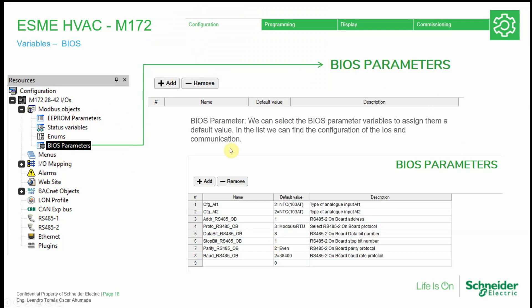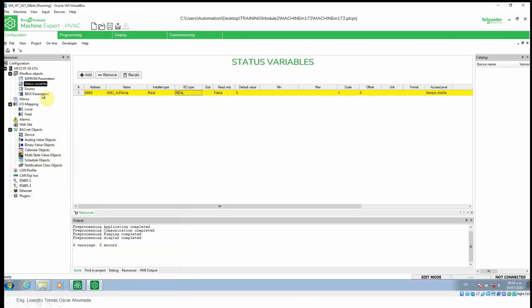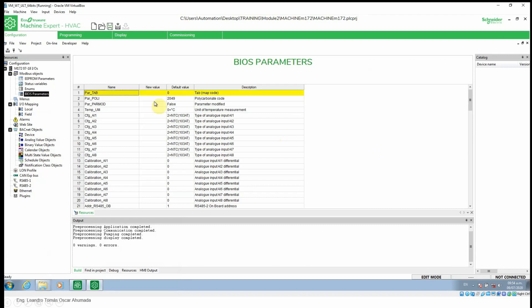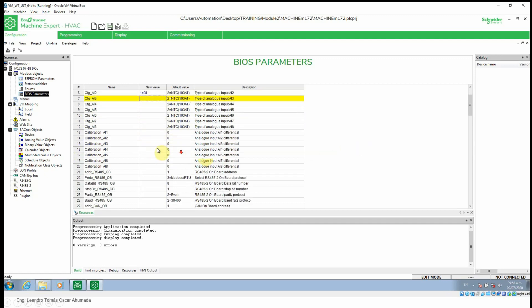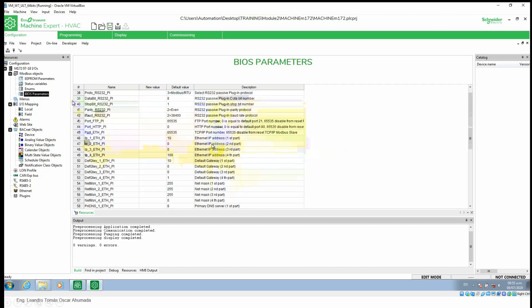Then we have the BIOS parameters. In this version of the software we have all the BIOS parameters — for example, for the analog inputs configuration we can select the configuration we want. In this PLC the configuration must be in pairs, so if we configure analog input 1 as digital input, analog input 2 must be digital input also. We have calibrations, and everything regarding the configuration of communications — Modbus, the plugin communication module. Going further, we can see the IP address.